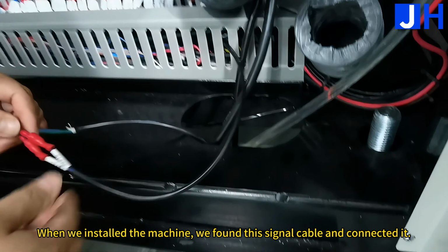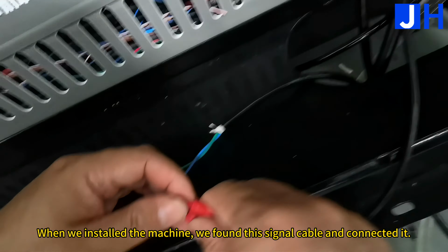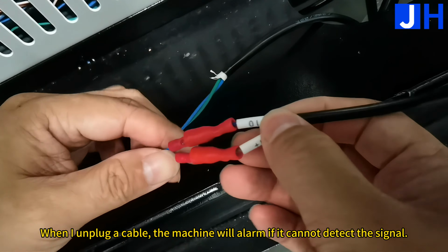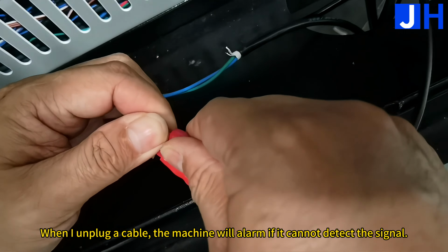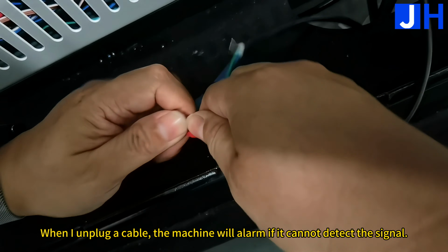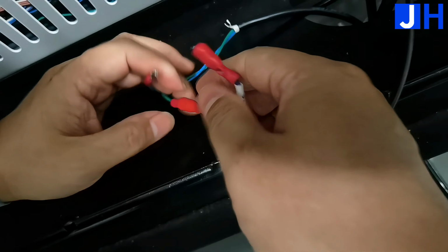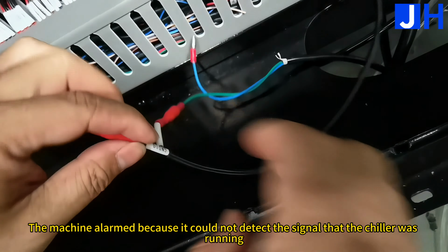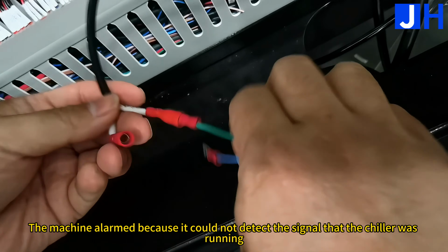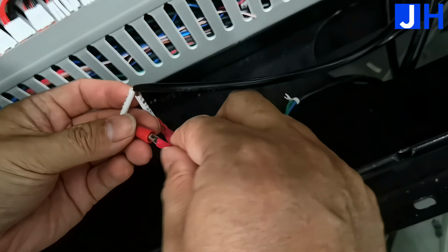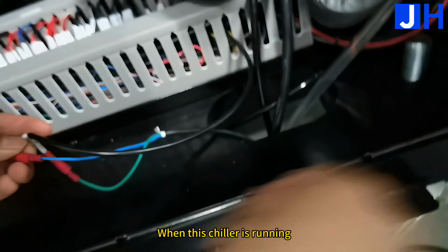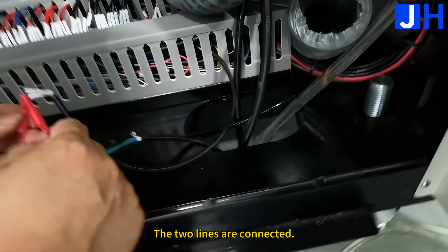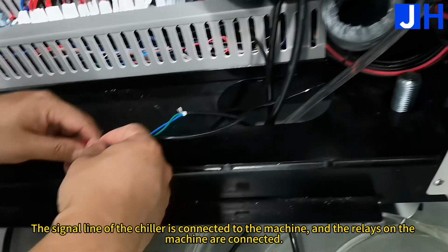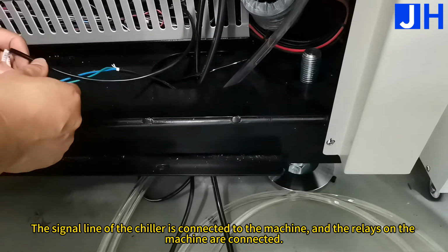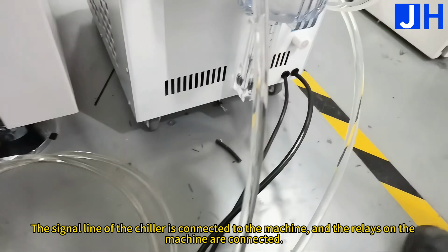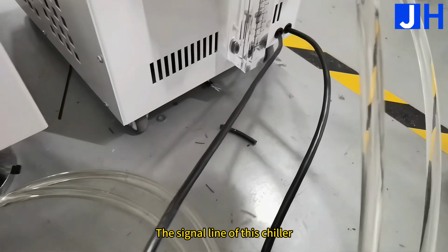When we installed the machine, we found this signal cable and connected it. When I unplug a cable, the machine will alarm if it cannot detect the signal. The machine alarmed because it could not detect the signal that the chiller was running. When this chiller is running, the two lines are connected. The signal line of the chiller is connected to the machine, and the relays on the machine are connected. The signal line of this chiller.